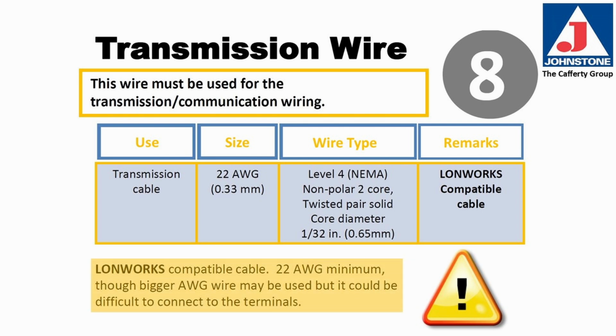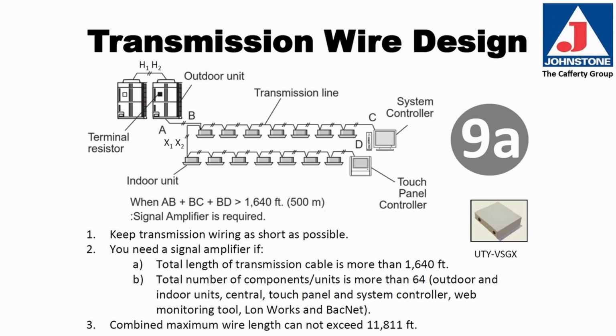LonWorks compatible cable, 22 gauge minimum, though bigger wire may be used, but it may be difficult to get the connections under the terminals, and too big a wire could cause communication problems. Transmission wire design. See the wiring schematic on this page. When lengths AB plus BC plus BD is greater than 1,640 feet, a signal amplifier is required. Keep the transmission wires as short as possible. You will need a signal amplifier if the total length of the transmission cable is more than 1,640 feet.